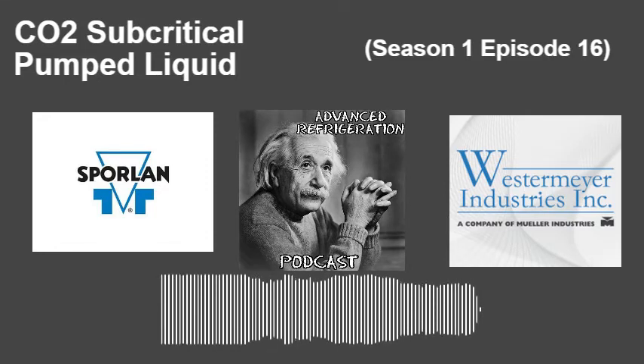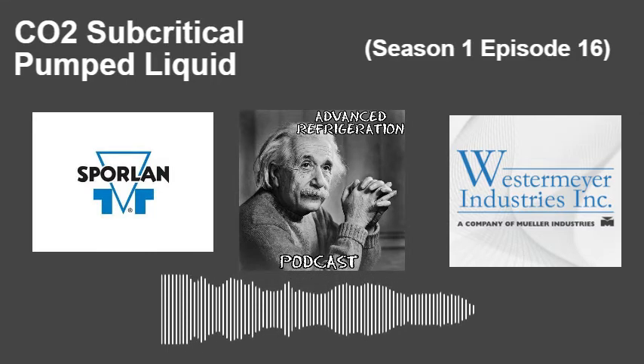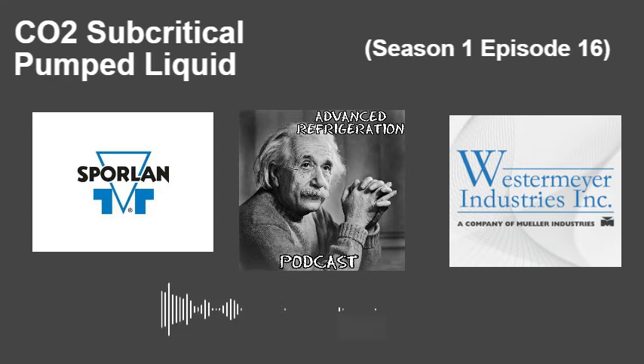I was going to say, you'll hear it referred to as a thermal siphon for any of you industrial guys out there. They have thermal siphon condensers that basically ensure that you have a full column of liquid at the bottom of there. There's usually some sort of line off the bottom to make sure that there's no air bubbles getting created when that CO2 drops down the bottom. Go ahead. That's all I wanted to add.